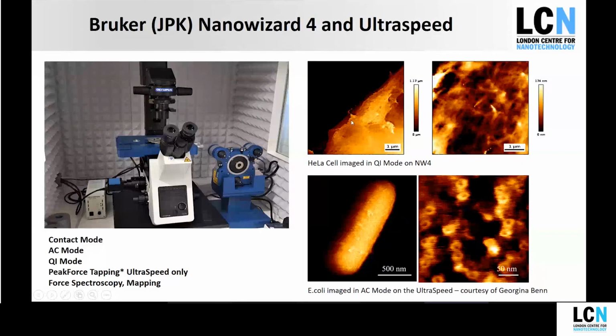Moving on to the Bruker JPK NanoWizard series. We have a NanoWizard 4 and an UltraSpeed. This one's the UltraSpeed, although the NanoWizard 4 looks very similar. Again, this is on a motorized stage and on an inverted microscope, another IX73. So we can in theory overlay optics and fluorescence again. The UltraSpeed itself is a fast scanning AFM for investigating dynamic processes. You can achieve line speeds of up to 100 Hertz.